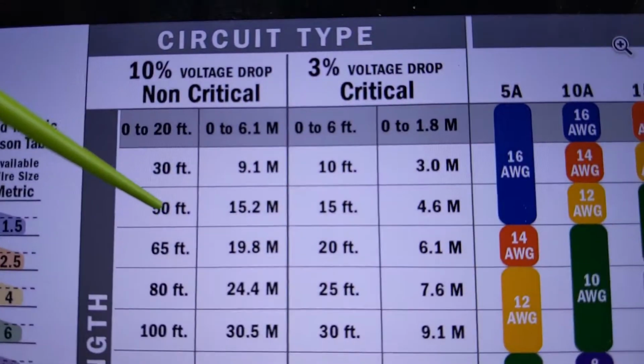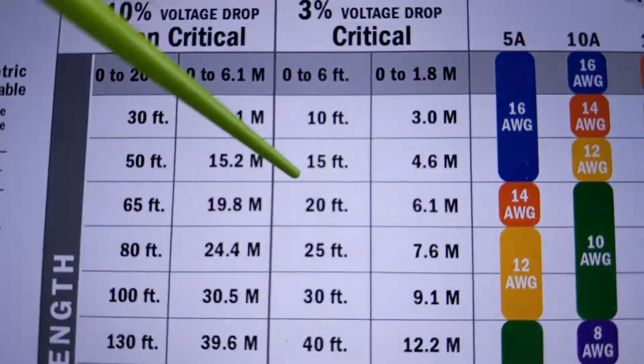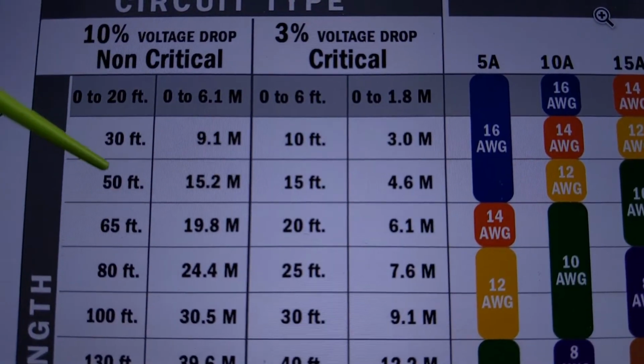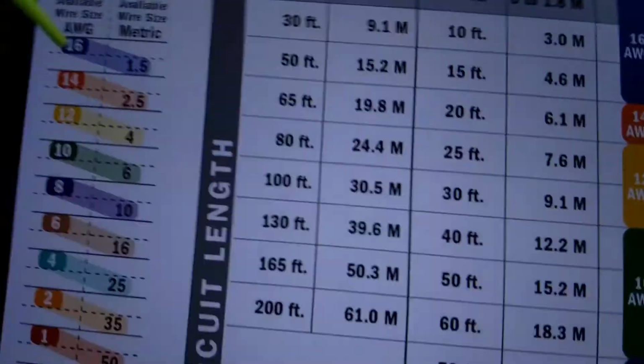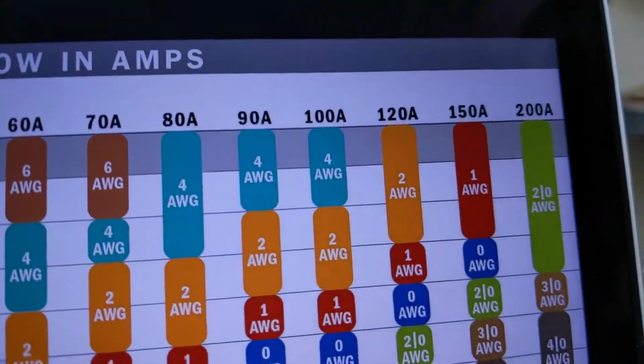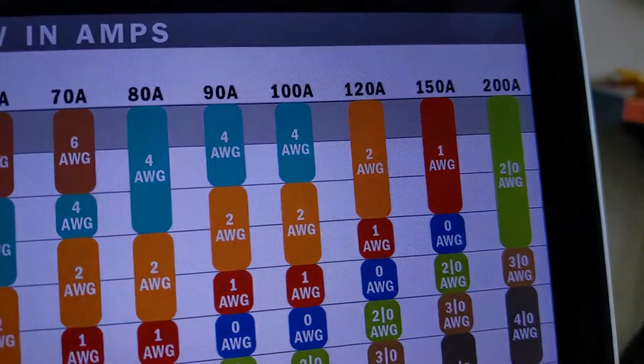And that's up to 15 feet if we want a 3% voltage drop, even further if we were fine with a 10% drop. So that's fine, that's good enough.